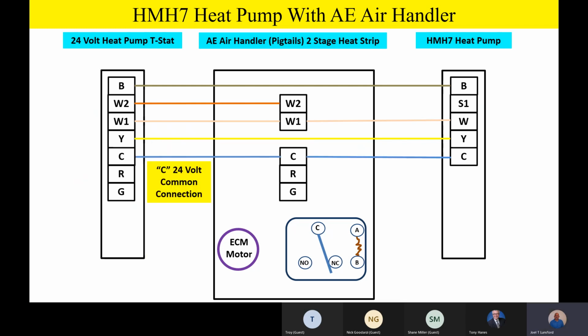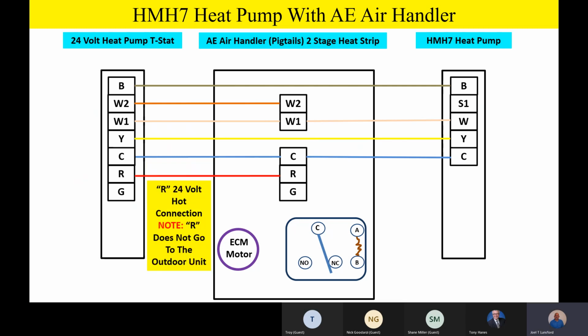C is our 24-volt common, and you'll notice that C terminal goes all the way through from the thermostat to the air handler to the outdoor unit. That's 24-volt common, goes all the way through. The R terminal from the thermostat goes strictly to the indoor unit. Now, let me repeat that one more time. The R terminal does not go outside. It goes from the thermostat to the indoor unit, but it does not go outside because the outdoor unit does not require an R terminal like all of our other products. So we're not powering up the board, so to speak, outside with the 24 volts from the indoor unit transformer. So we do not take R outside.